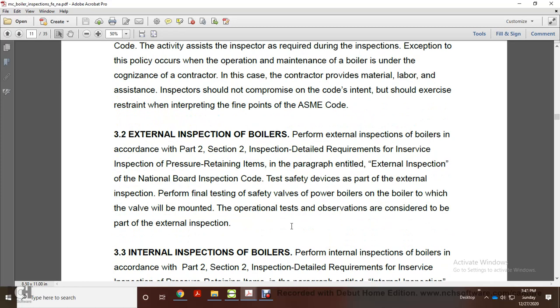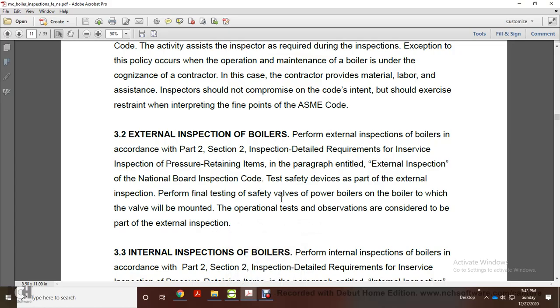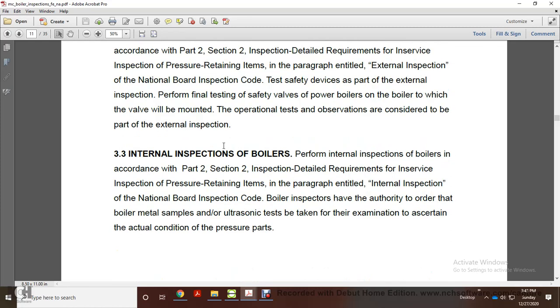3.2 External inspection boilers. Perform external inspection of the boilers according with Part 2, Section 2, and Inspection-Detailed Requirements for the in-service inspection pressure-retaining items of the paragraph entitled External Inspection for the National Board Inspection Code. Test safety devices as part of the external inspection. Perform final testing of safety valves of power boilers on the boiler to which the valve will be mounted. The operational testing observation are considered to be part of the external inspection.